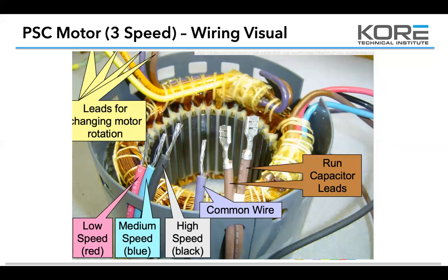The difference between looking at a run cap and a start cap, guys, if you don't know: run caps usually have low microfarads. Start caps usually have high microfarads. Start caps are usually brought into play for a fraction of a second for the kick, and then a relay or something is used to drop that start capacitor out of the circuit, and keep the run in play. Make sense? Any questions?